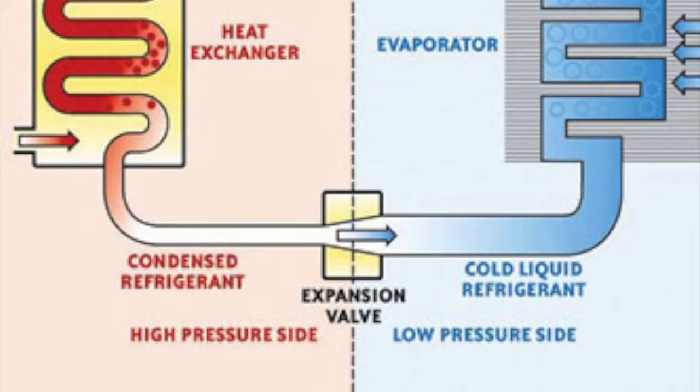Back in the heat pump, we now have this cooler, less excited propane that's given away a lot of its energy to the hot water, but it's still under a little bit of pressure. So we run this through an expansion valve — you might call this a throttle. An expansion valve is basically the opposite of a compressor. Running it through the expansion valve, we are now left with a low pressure and low temperature liquid, and that liquid is ready to run back around again to the evaporator and the big fan to take some more heat out of the air. And that is the heat pump process — that is how a heat pump works.